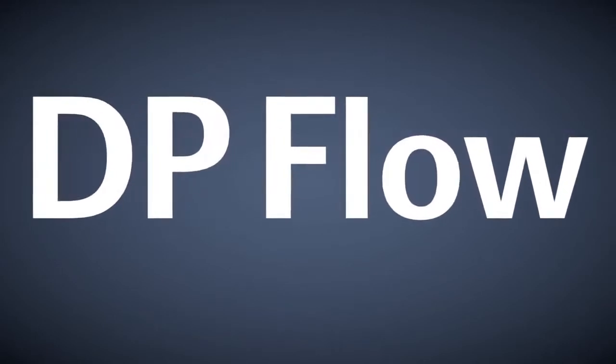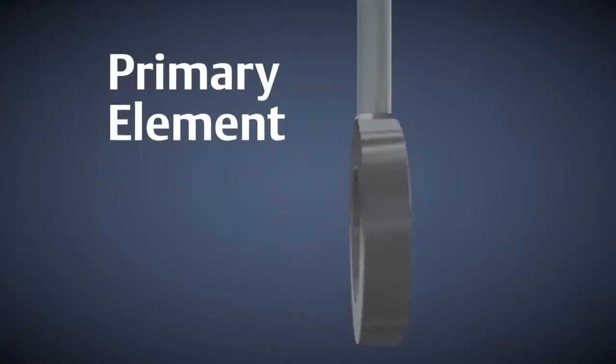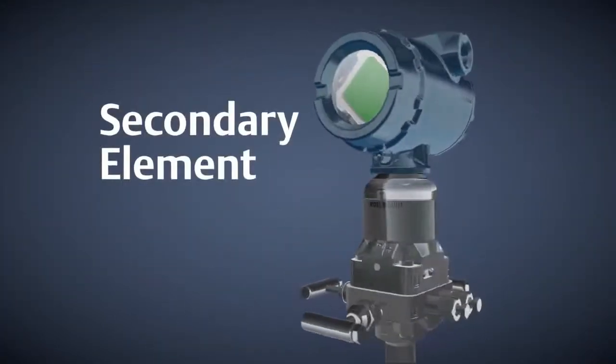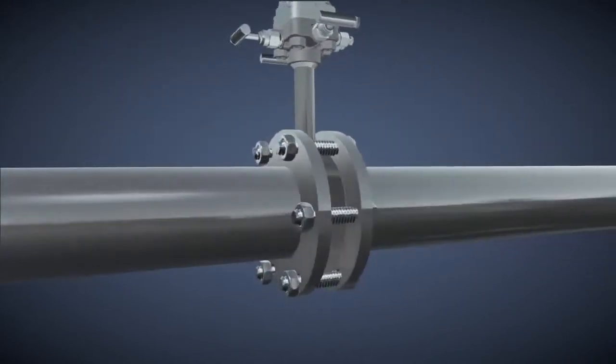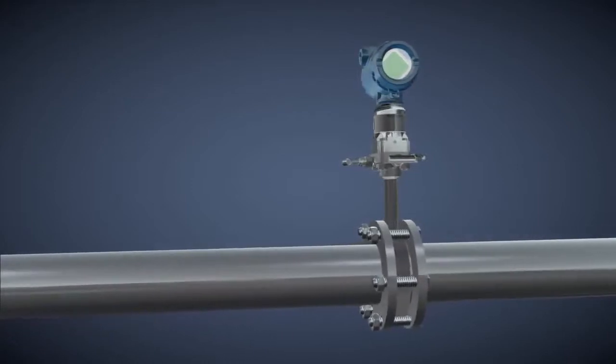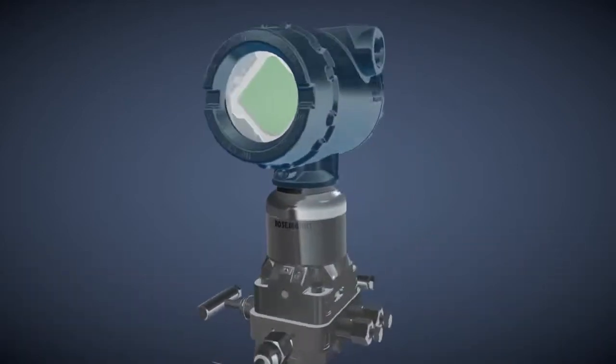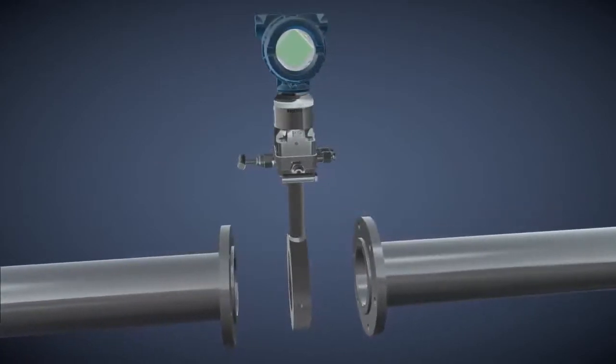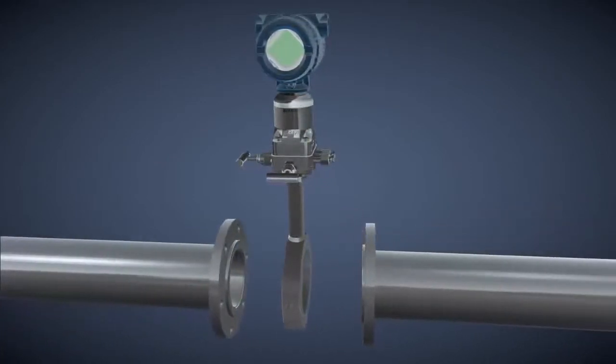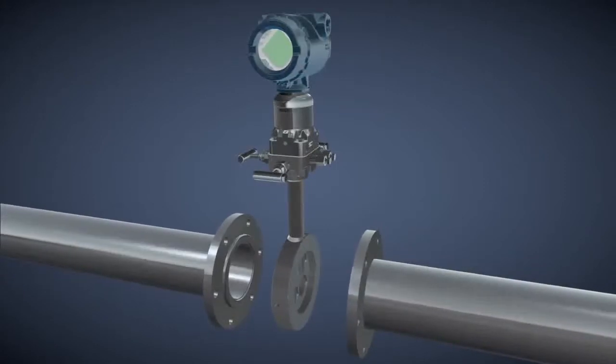DP flow is measured with a combination of a primary element and a secondary element. A primary element is placed in the pipe to create a differential pressure while connecting the secondary element to the process. The secondary element, or transmitter, takes measurements from the primary element and converts them into useful quantitative values and transmits those values to a control system.